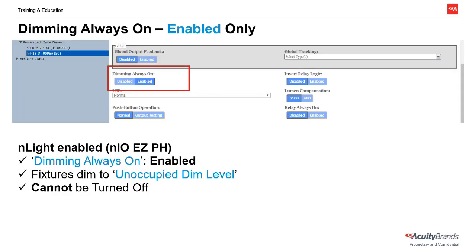For an NLIGHT enabled fixture, enabling Dimming Always On will force the lights to stay on even if a switch is used to attempt to turn them off. The lights will simply dim to the unoccupied dim level and remain there. Note that this setting does not affect the user's ability to dim the lights up and down, just the ability to turn them off.